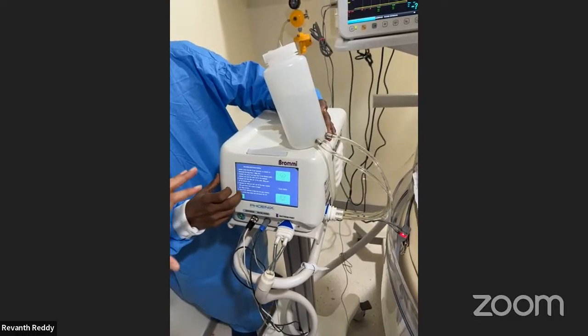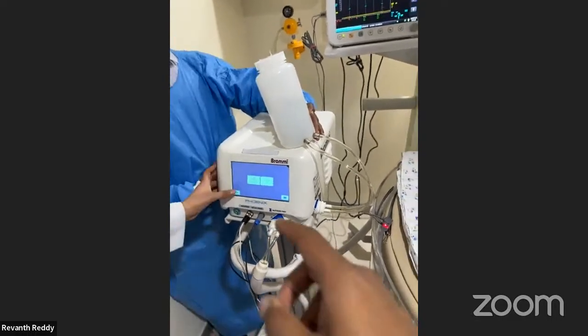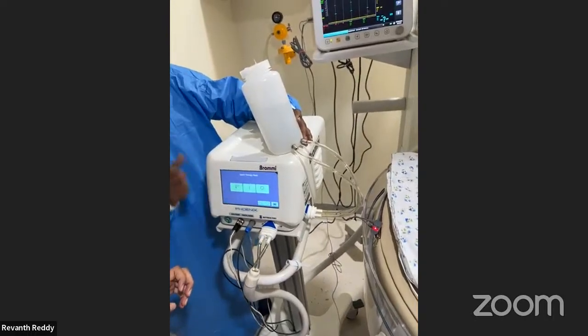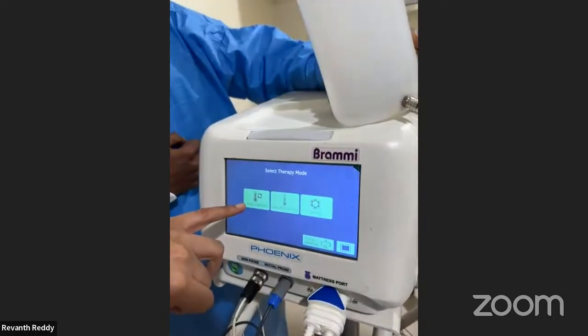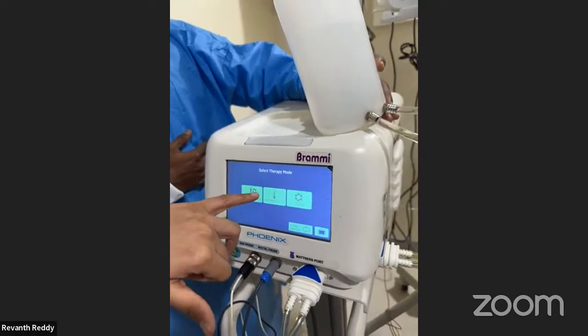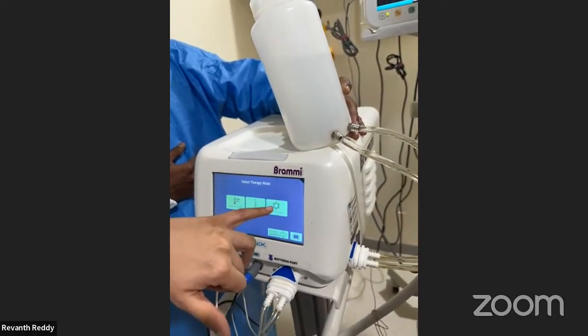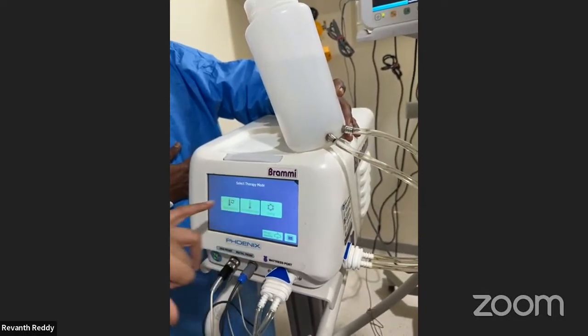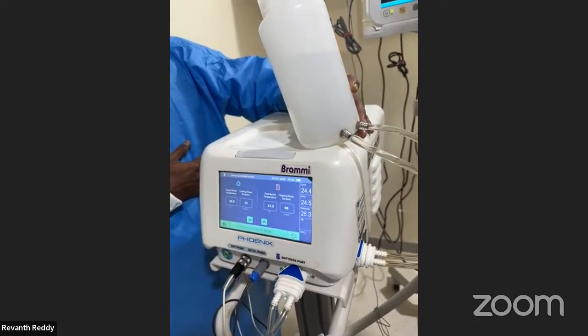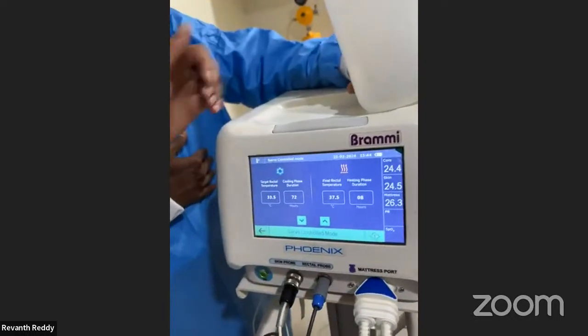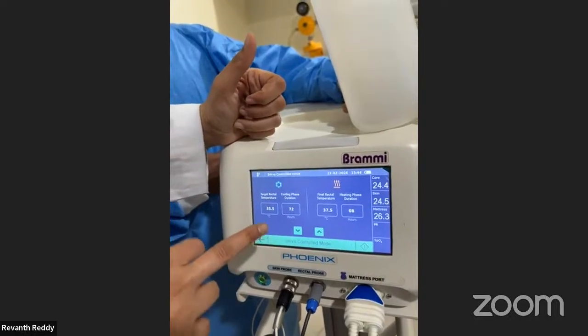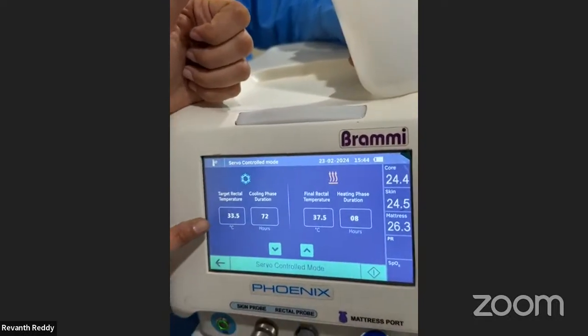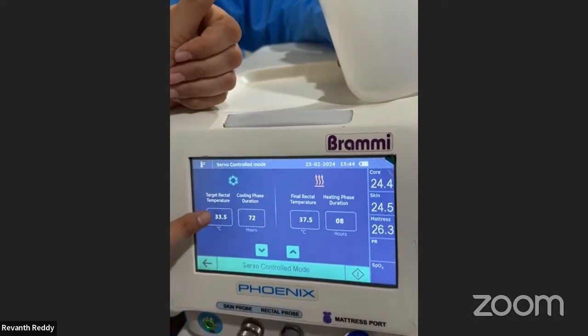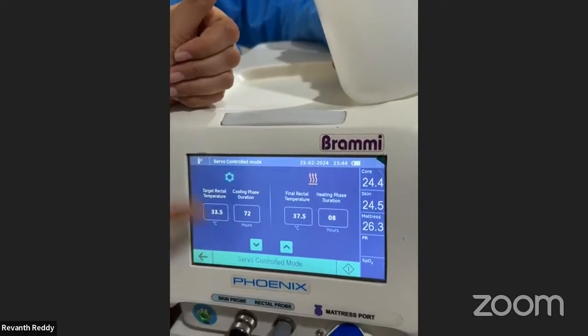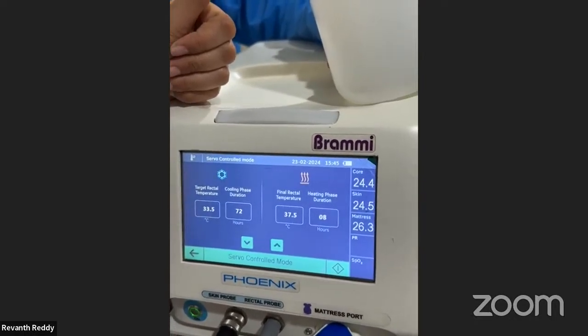So once you go to the main mode, you will find the options. So you have the servo controlled cooling mode, the constant mattress temperature, as well as the cooling mode. So generally we will be choosing the servo controlled cooling mode. Once you click this, you will get different options. So you can choose what is the target rectal temperature. Generally this is chosen as 33.5 degrees Celsius. The variation can be plus minus 0.5.